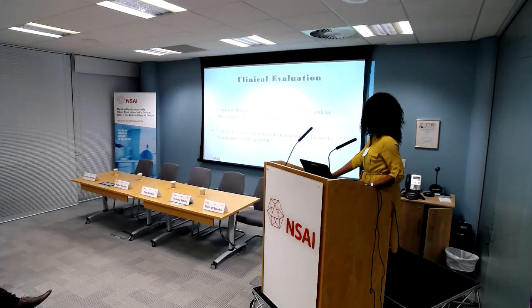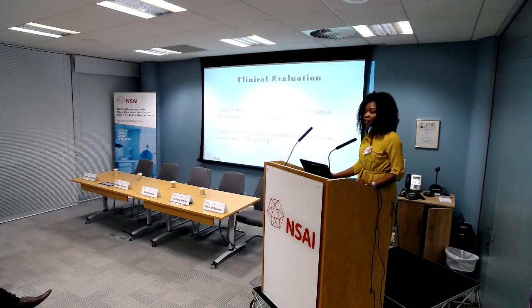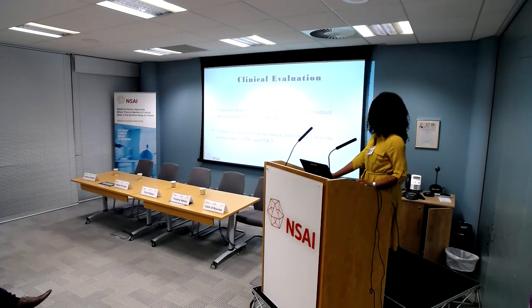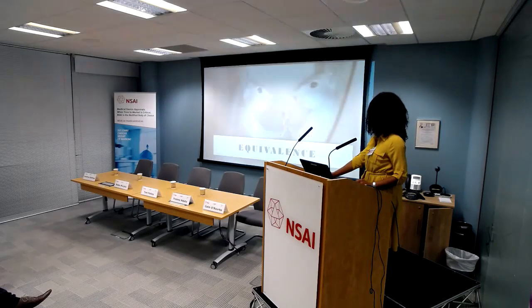So as I said earlier, you have to keep proactively looking for any data related to your device. Clinical evaluation is a continuous process, and you have to keep documenting every piece of clinical evidence you have on your device throughout its life cycle. You would also include your PMS data, which is your post-market surveillance data, so how your device is performing in the clinical setting, in your CER, and also information on your PMCF, which is post-market clinical follow-up.